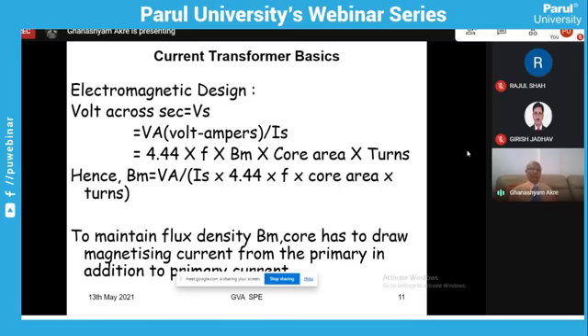That is, any voltage across the secondary or any winding is equal to 4.44 multiplied by frequency, multiplied by flux density, multiplied by core area, and the number of turns. So on that basis, you can see the flux density will be equal to VS divided by 4.44 F, core area and turns. This will give you the flux density. The significance of the flux density is there, which I will explain further.